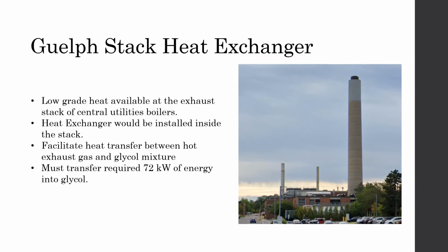The University of Guelph campus has a large exhaust stack that outputs a large quantity of hot flue gas. This flue gas is a source of low-quality heat, which is capable of providing enough energy to effectively heat the glycol used in the hydronic system. To transfer this heat, a heat exchanger will be installed inside of the stack.